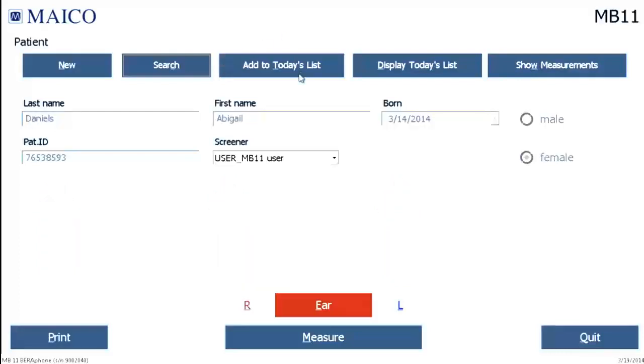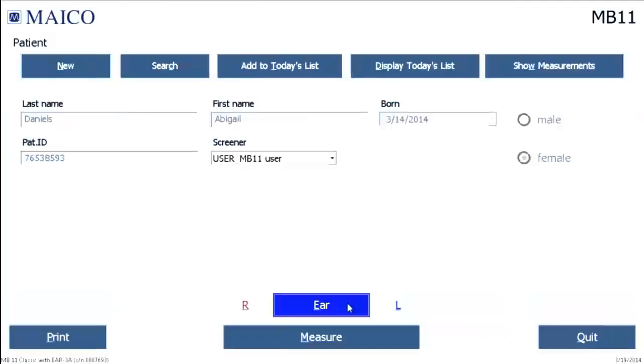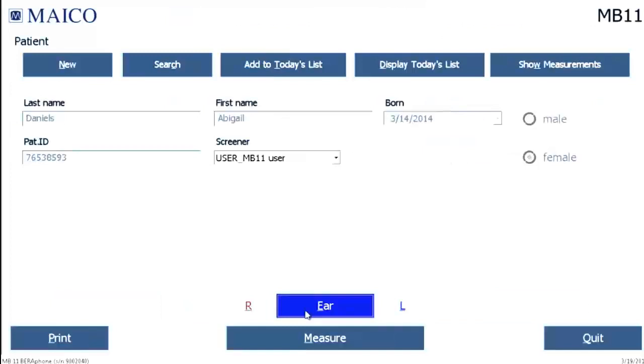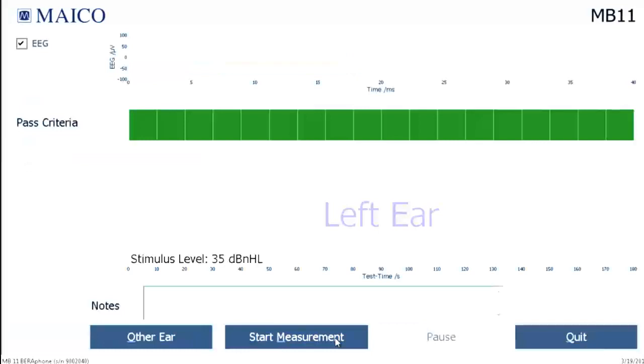Select the ear you want to test first by clicking on the right or left symbol, or by clicking on the Ear button until the correct ear is chosen. When the background of the ear button is red, the right ear is selected. When the background is blue, the left ear is selected. If you're using classic hardware, it will be possible to click on the ear button until the background color is pink, which sets up for testing both ears simultaneously. When the ear is selected, select the Measure button to proceed to the measurement screen. When the baby is prepared for screening, select the Start Measure button to begin the screening.